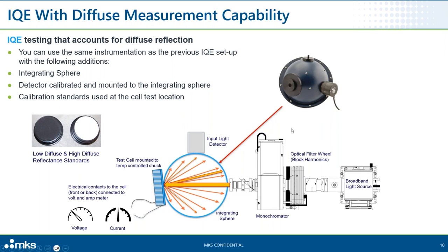And in this case, again, similar to what I showed previously with the high and low reflectance calibration mirrors, we would use diffuse low and diffuse high reflectance standards to again calibrate the system prior to doing your IQE testing.